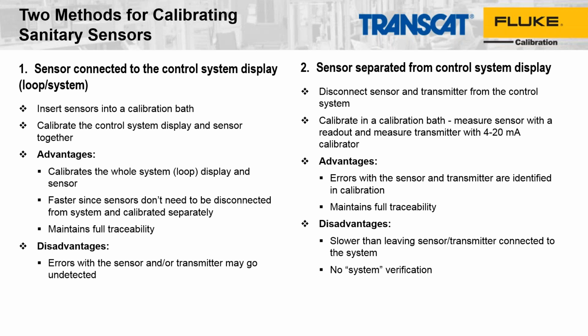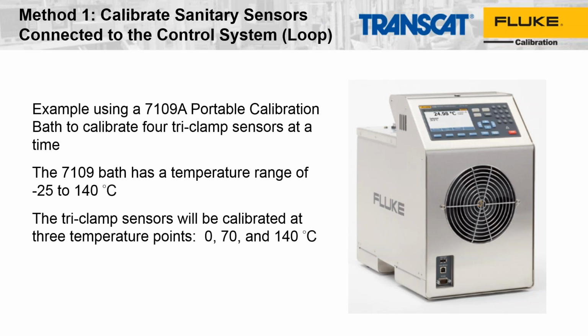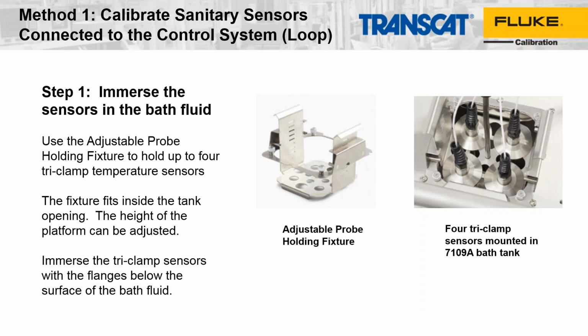So in this example, we'll be using a 7109A bath that goes from -25 to 140, and we've just selected some temperature points to be an example of what you could do. So 0, 70, and 140. So the first step is to take the tri-clamp sensors out of the tri-clamp system and place them into the bath. You can place them into this probe holder fixture to help hold them up while you get them all set up, and then use it to the sensors.